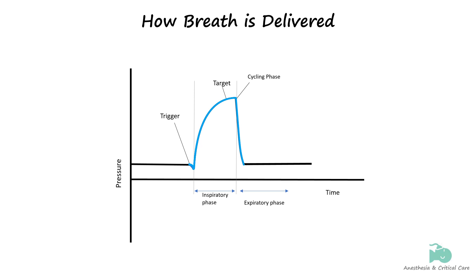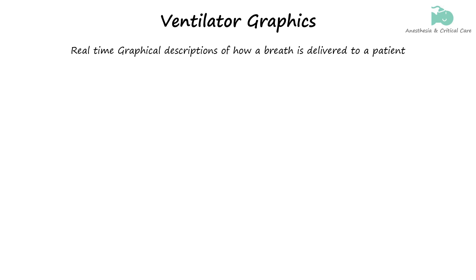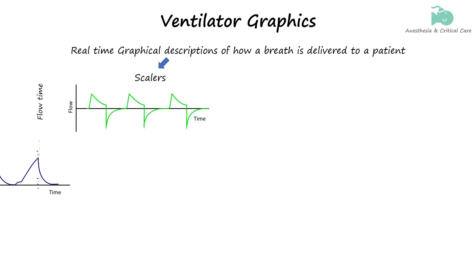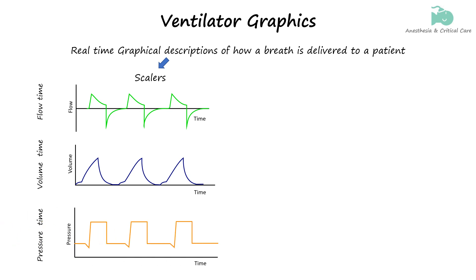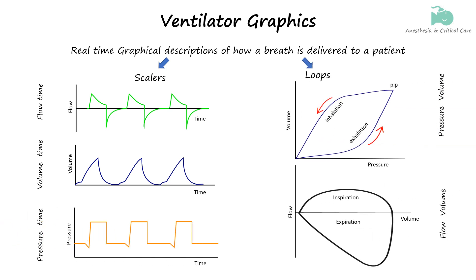Any combination of these variables can define the type of breath delivered by the machine. Ventilator waveforms, or ventilator graphics, are graphical descriptions of how a breath is delivered to a patient. These include three scalars — flow over time, volume over time, and pressure over time — and two loops: pressure-volume and flow-volume loops.